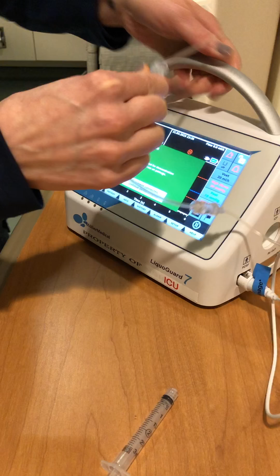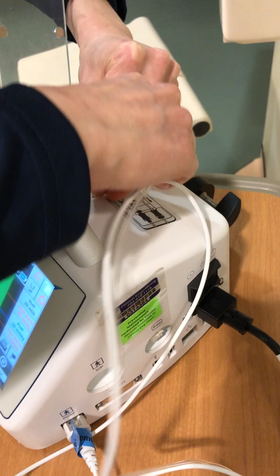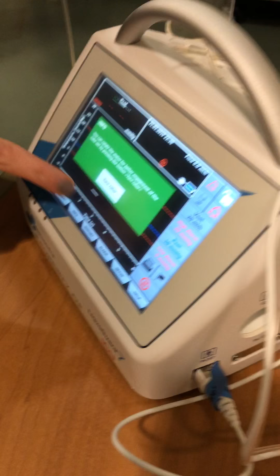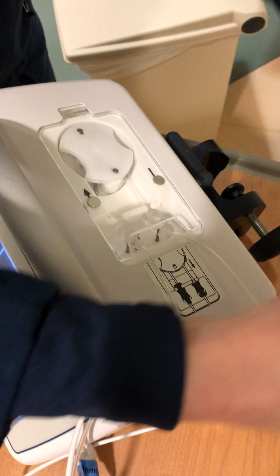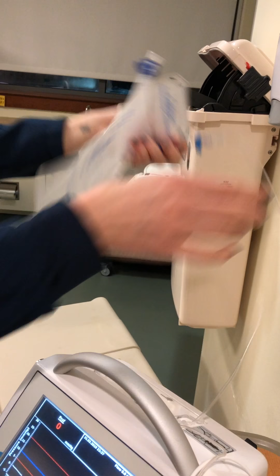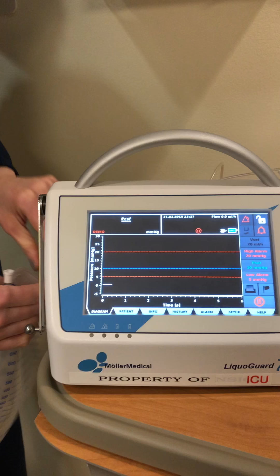patient's lumbar catheter in their back, and then you're going to plug this portion into here, and then you're going to have to load the tubing into the top of the machine. So you want to flip up this panel here. You're going to attach the first part of the catheter in here, and then you want to go to your screen, and this will pop up, turn rotor. So you have to press and hold it down and just let it take in the catheter tubing. Okay, and go ahead and close it.